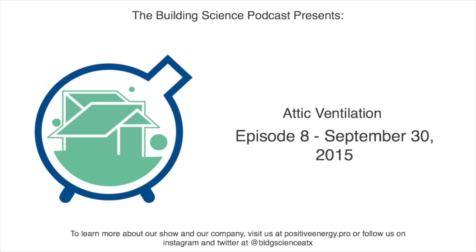And in that attic ventilation scenario where you're paying to pull air out of it, except for selling more ventilators, there's really no good reason to do that from an energy perspective. You use more energy to pull air out of your house up into your attic, running that vent fan, vastly more than you'll ever save from doing that. So this is a big example of something that's never been measured. I mean, maybe there is an effect, and it's in the noise. It's just never been strongly correlated with it. Again, you could look to the research by Danny Parker, Steve Brick, Bill Rose, for a lot more background on all this stuff. I'm speaking somewhat extemporaneously on this today. So number 3, lower cooling bills, not data-driven.